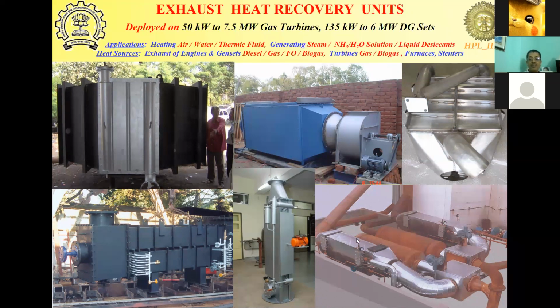Now, this is dirty and sooting in nature. So we have multi-modular heat recovery with sonic soot blowers and online soot cleaning mechanisms like compressed air or steam-based soot blowing, so that the heat exchangers can continue to operate while the cleaning of the heat exchanger is happening. We don't have to take a shutdown.